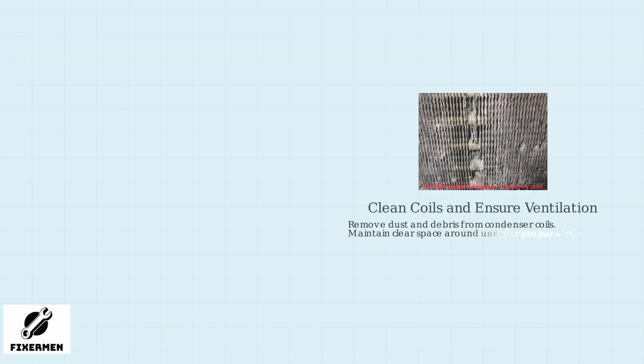Clean the condenser coils regularly to remove accumulated dust, dirt, and corrosion. Clogged coils impair heat dissipation, leading to compressor overheating. Ensure there's adequate ventilation around the outdoor unit by keeping it at least 2 feet clear of walls, plants, or debris. Poor ventilation is a common cause of E4 errors in residential settings.